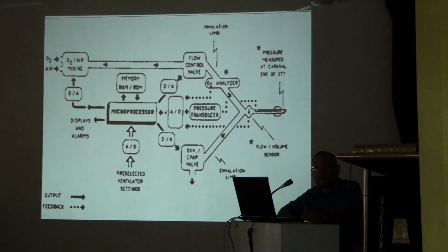Now what you have to assure? You have to assure that the patient is getting the desired FiO2 that I have decided. Normally, all machines have a master control so that they can never deliver air below 0.21 FiO2. Why 0.21? Because 0.21 is the basic necessity for a human being. Without the basic 0.21 delivery, human life is non-sustainable. So you have to monitor what percentage of air or oxygen I am giving to the patient. Whether it is the desired one, I have said here, say 50% oxygen, 50% nitrogen. Nitrogen is the other carrier gas in the air. So you have to check whether this component of the machine has worked properly or not. Because this, after all, is a machine. It is an idiot. An idiot can fail any time. I have set the dial to 50% oxygen, but I have to check whether the machine is able to deliver 50% or not.